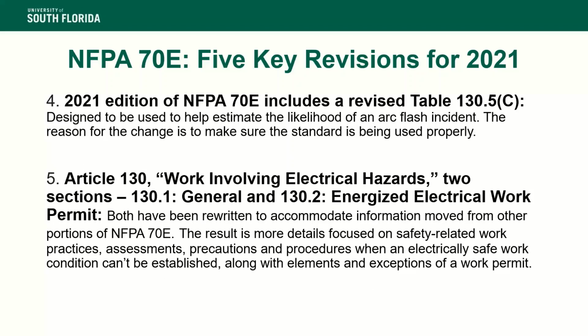The fourth revision was that they included a revised Table 130.5(C). Keith talked about that earlier in his presentation. This is designed to help estimate the likelihood of an arc flash incident. The reason for the change is to make sure the standard is being used properly. The last revision was done to 130.1 and 130.2, the general requirements and the energized electrical work permit. They've been rewritten to accommodate information moved from other portions of NFPA 70E. The result is a more detailed focus on safety-related work practices, assessments, precautions, and procedures when an electrical safe work condition can't be established, along with elements and exceptions of a work permit.